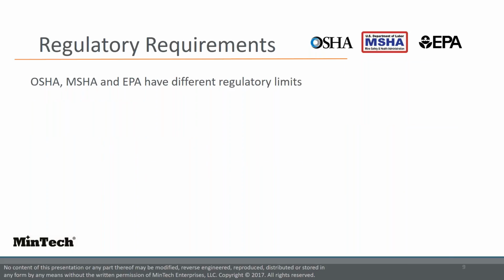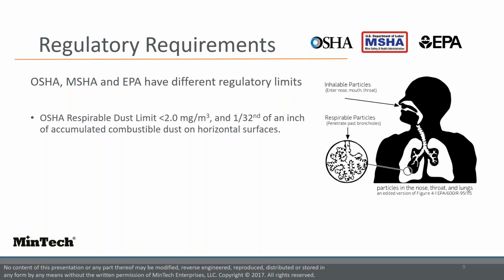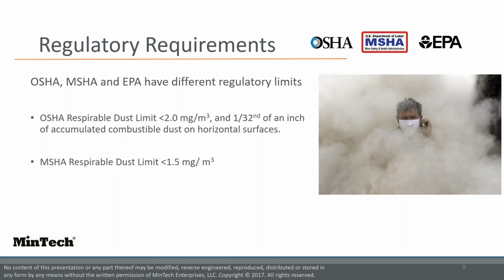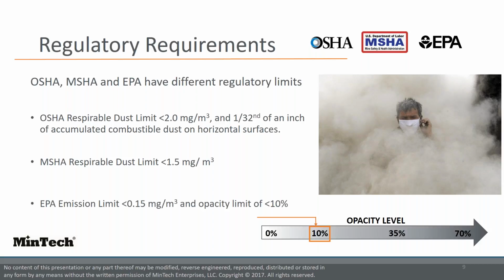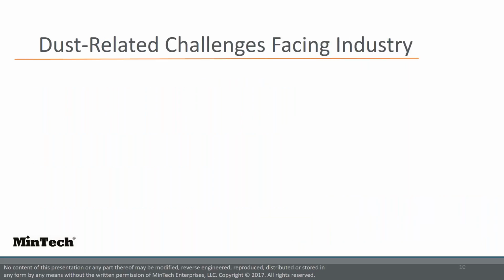The regulatory limits imposed by each agency are similar, but do vary slightly. OSHA's respirable dust limit is actually 2.0 milligrams per cubic meter, averaged over 8-hour periods. OSHA also requires combustible dust accumulation to be less than 1/32 of an inch. MSHA's respirable dust standards are 1.5 milligrams per cubic meter, also averaged over 8 hours. And the EPA emission limit is 0.15 milligrams per cubic meter over a 24-hour period of time. And the opacity limit set by the EPA must remain 10% or less in a dust cloud.